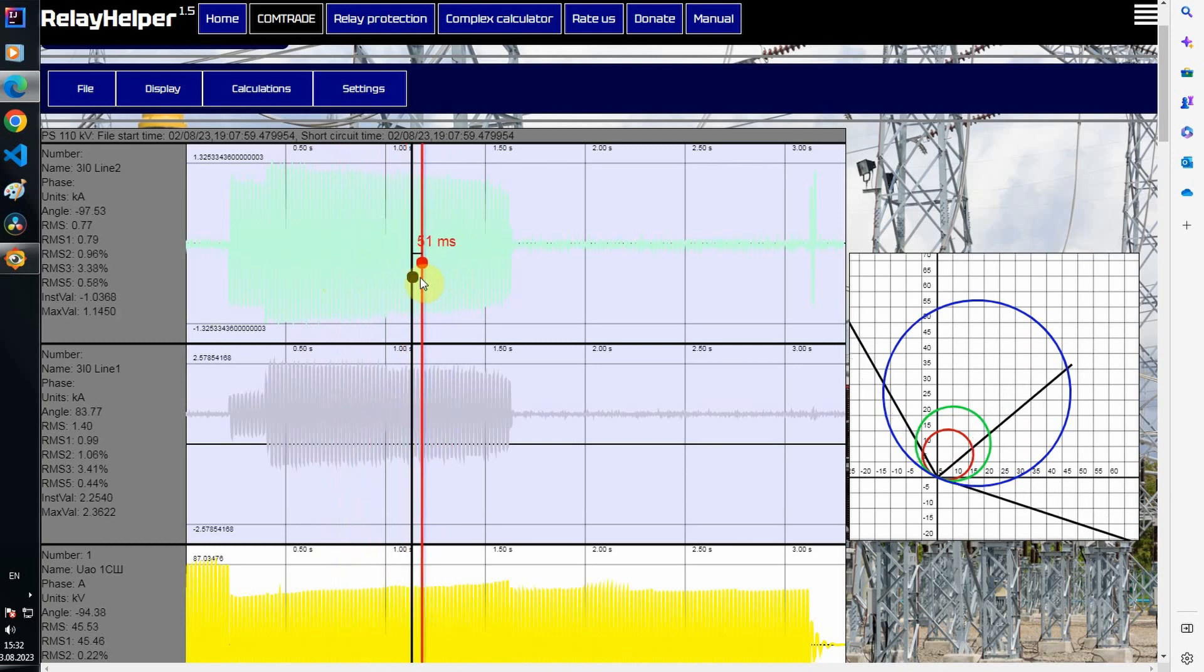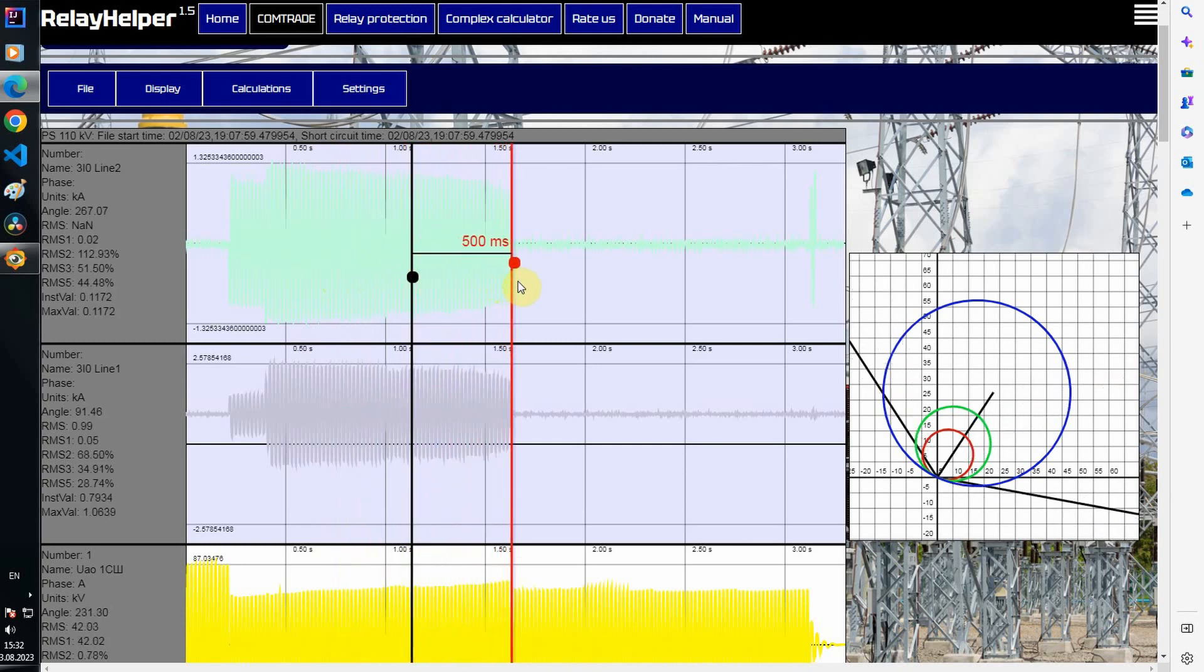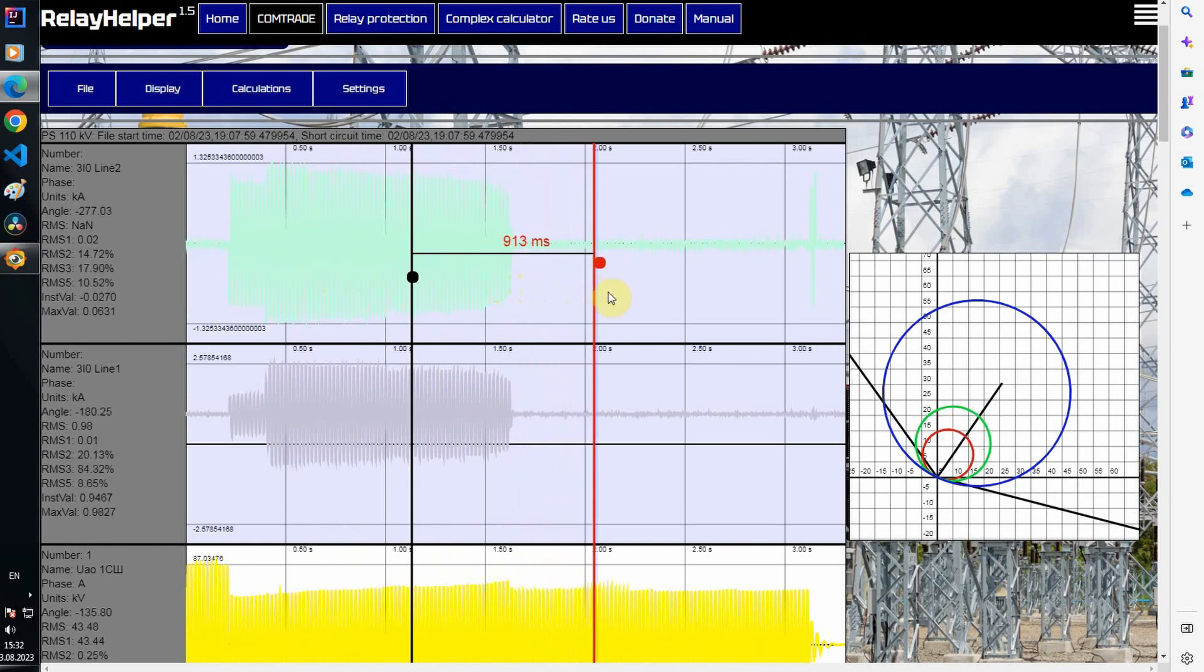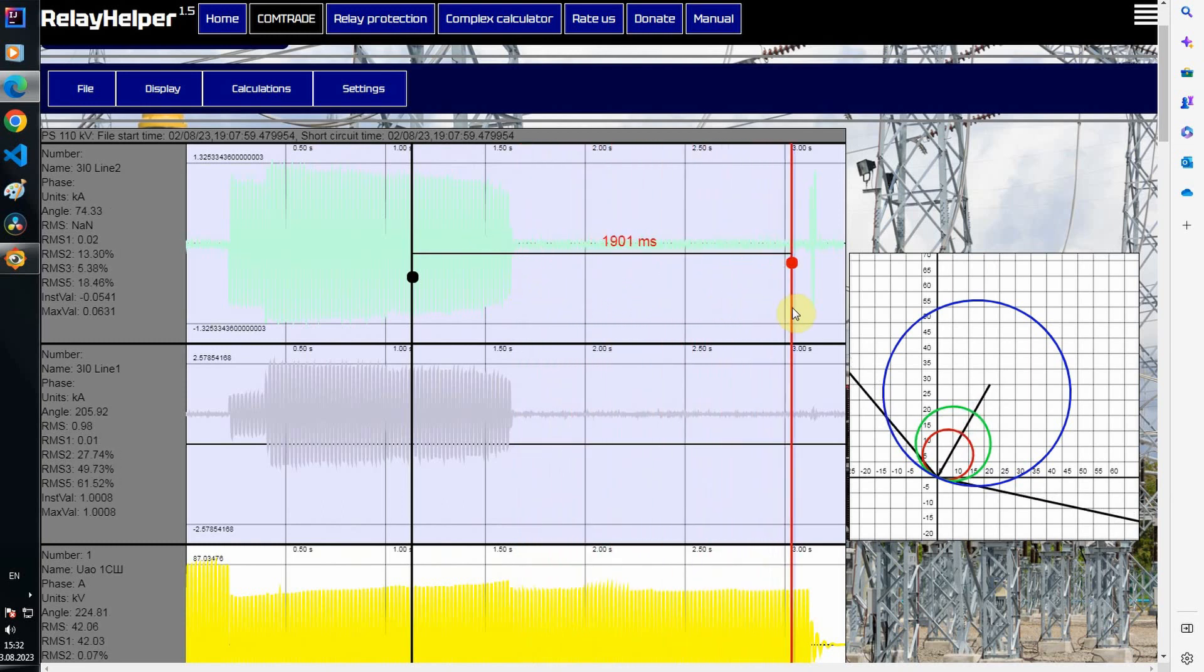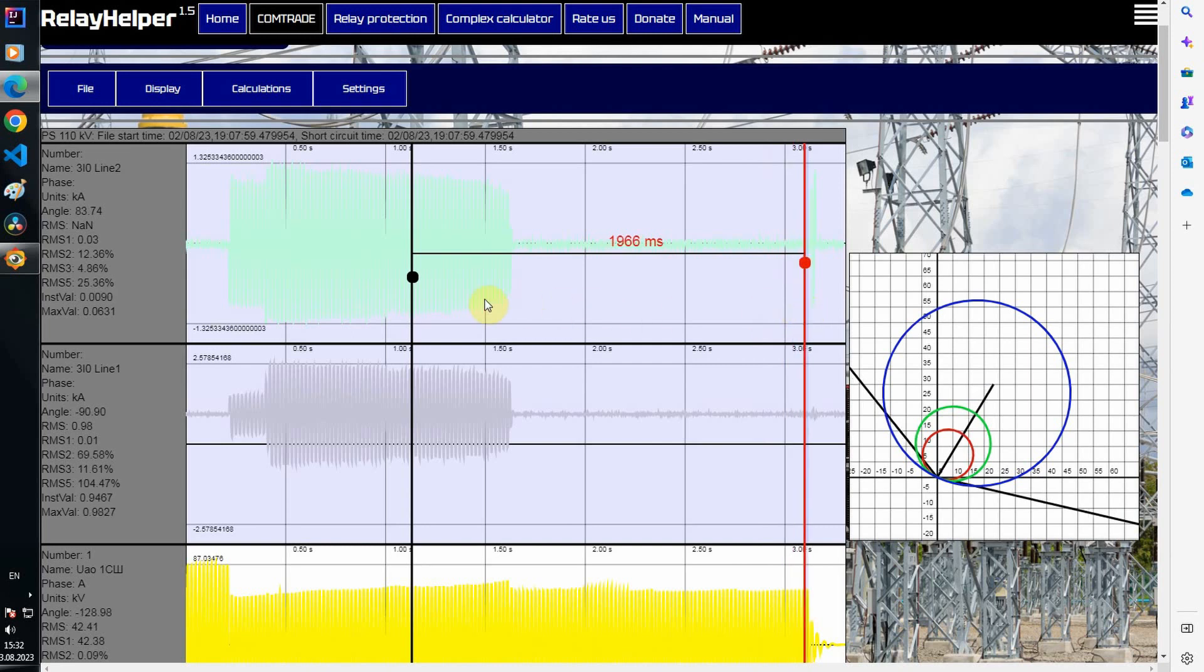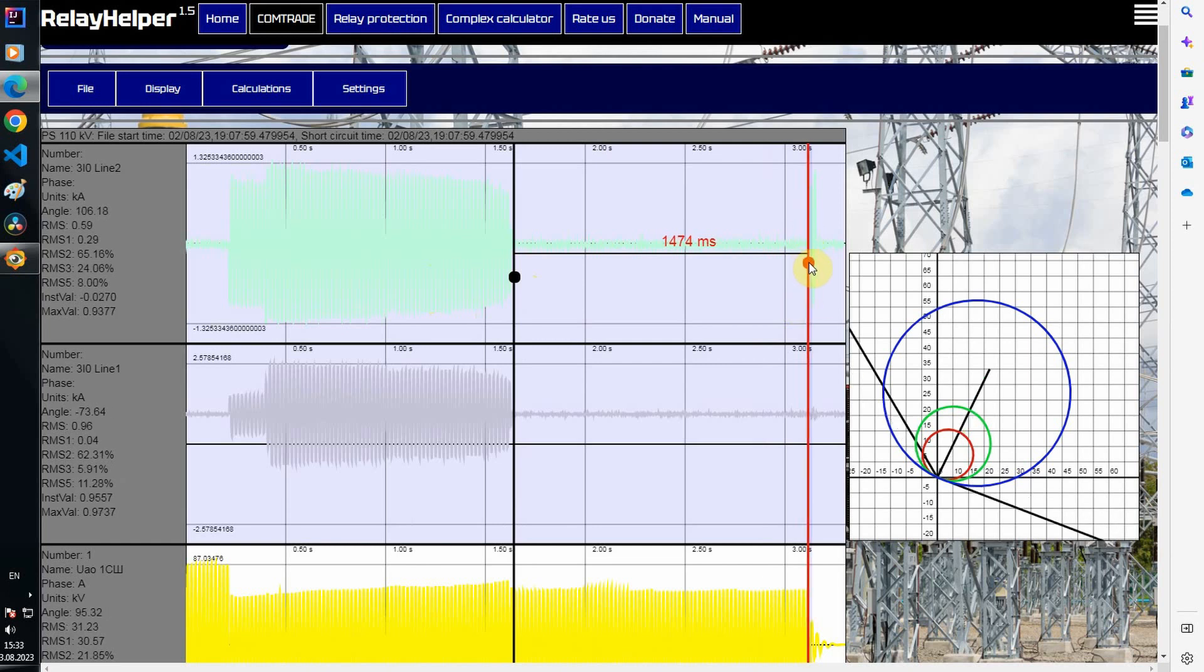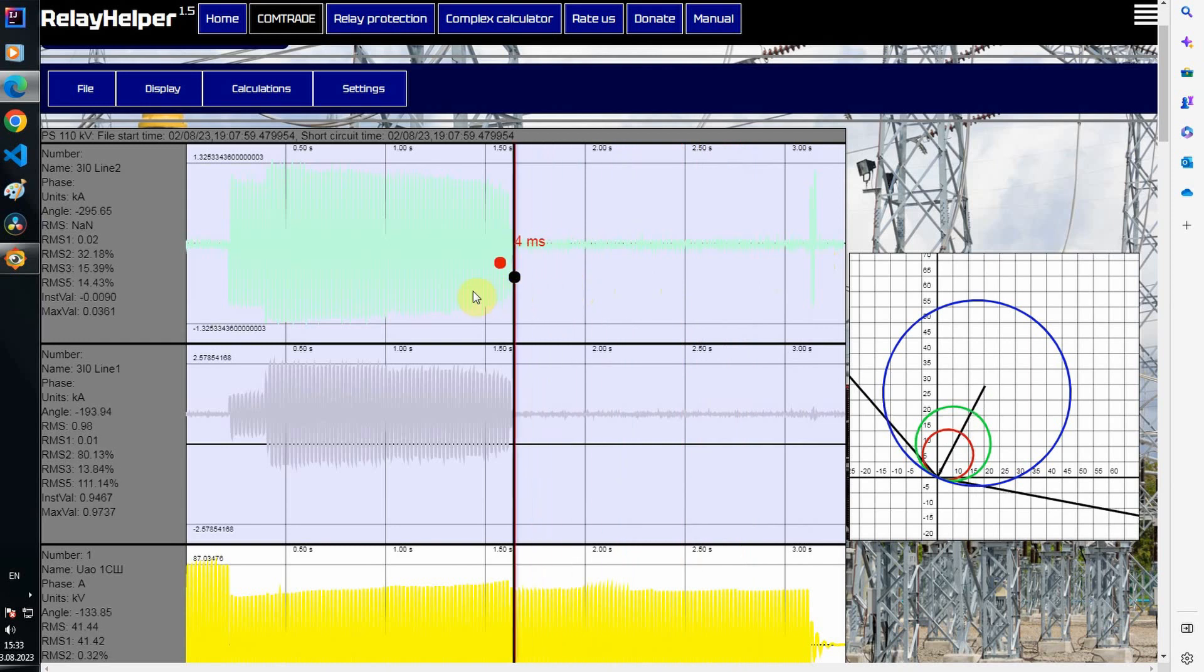He's out of bounds here and here again in the third zone. This zone time is 4.2 seconds. It did not have time to work and the trip occurred on the other side.